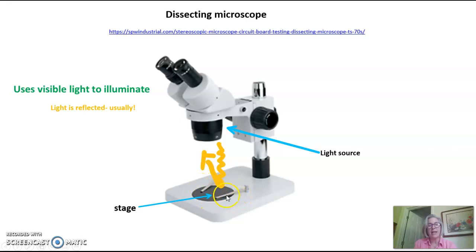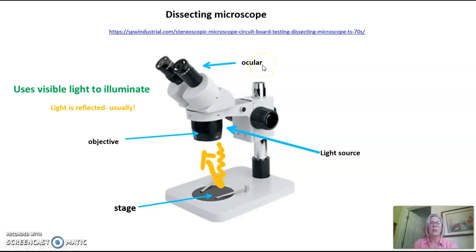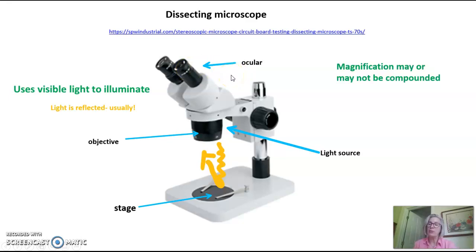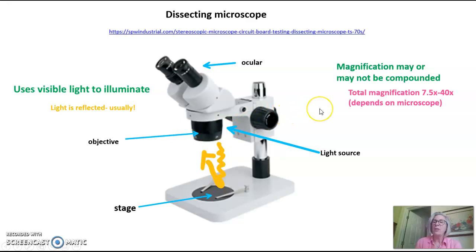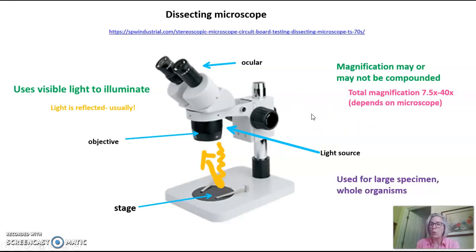Your specimen sits on the stage, and the light bounces off it and comes up to the objective — this large circular piece — where the first magnification occurs. The light then goes up through the ocular. These oculars may or may not provide a second place of magnification, so sometimes dissecting microscopes compound the magnification, and sometimes they just have the magnification of the objective. The total magnification is very low — between 7.5x and 40x — so think of this dissecting scope like a magnifying glass that you don't have to hold.